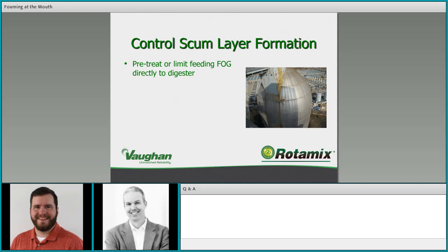Controlling scum layer formation: pre-treat or limit feeding FOG directly to a digester — you don't want to push a big slug of FOG in all at once. Many facilities have a receiving station with some capacity so FOG can be metered into the digester. There's also something to be said for pre-treatment or hydrolysis of FOG to break down grease and fats into long-chain fatty acids, making them more soluble and less likely to create a surface layer.